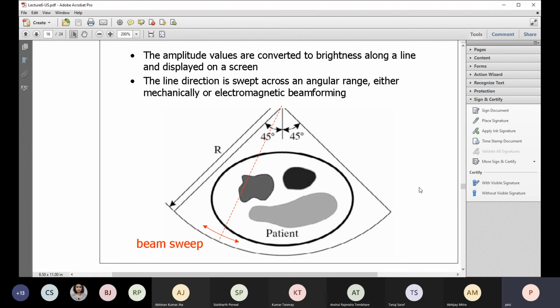However, because in ultrasound we have another piece of information, that is time, which is very useful. If we code the time, more or less the depth information is known. So using these two together, we can have better imaging. That means using the tomography principle we can reconstruct a certain amount of information, and then by depth coding with respect to time we will get additional information. So using these two we can do better reconstruction.